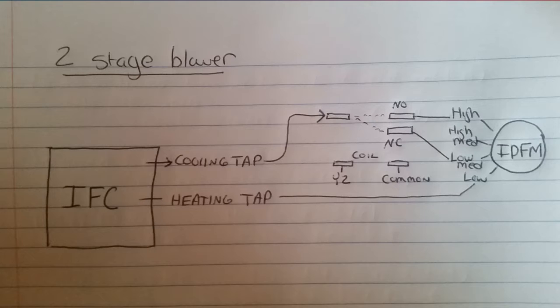If you see in the picture, we have an IFC integrated furnace controller with a cooling tap and a heating tap. We can sort of ignore the heating tap. It's just there to show us that there's going to be two taps on these boards, one for your cooling tap for your PSC motor, one for your heating tap. Typically, the heating tap is a lower speed, although it doesn't have to be. In some instances, it may be higher, but for this case, we're going to go with the typical, which is a lower speed.